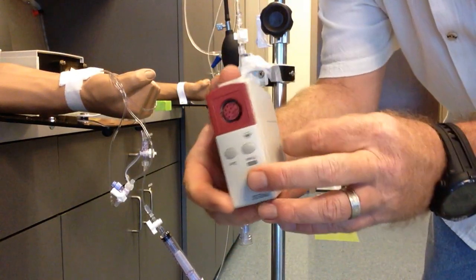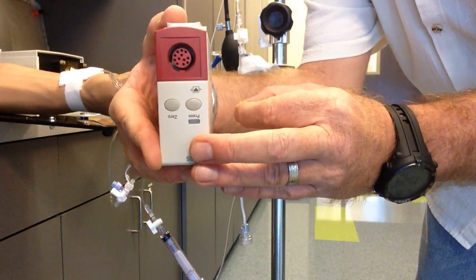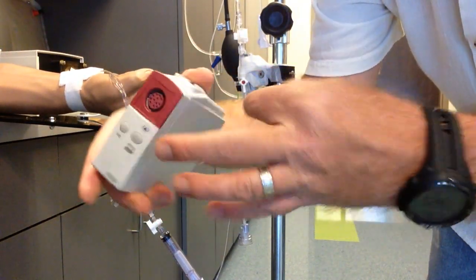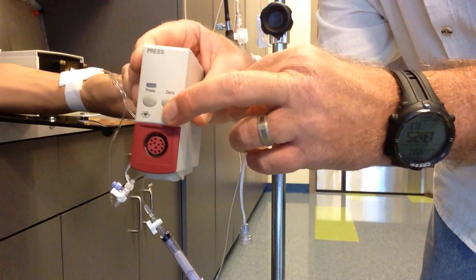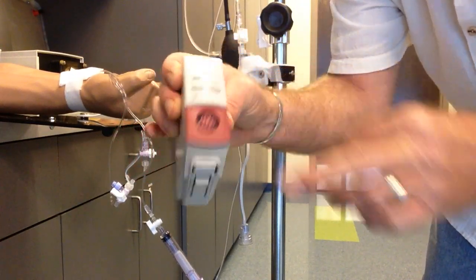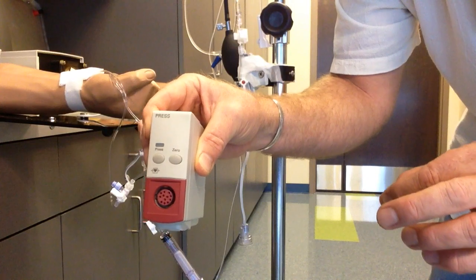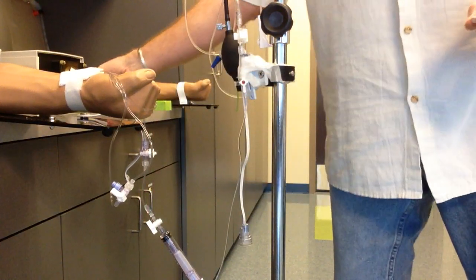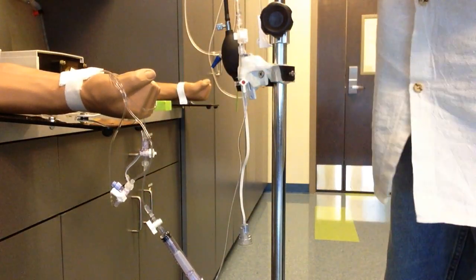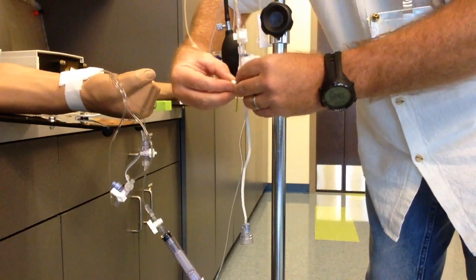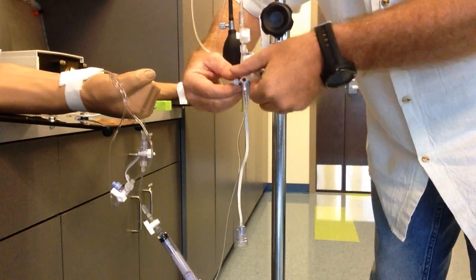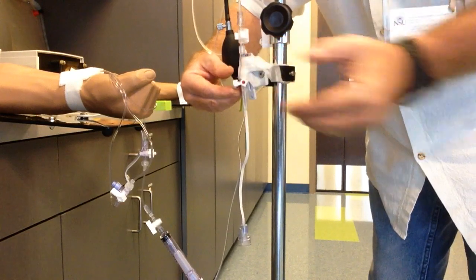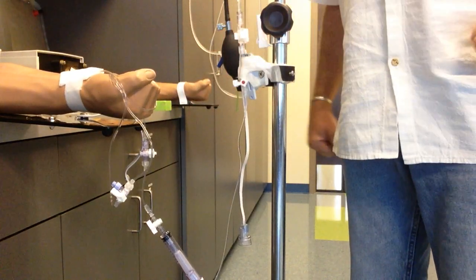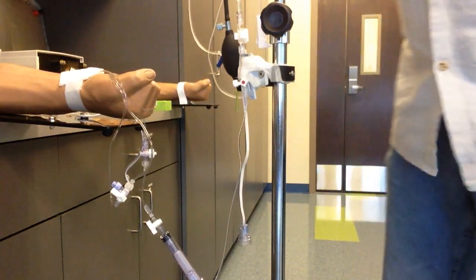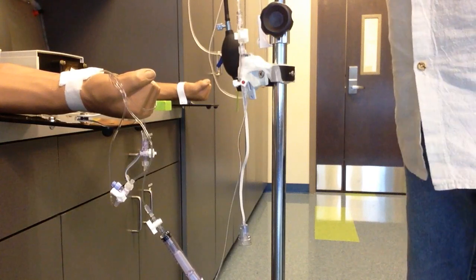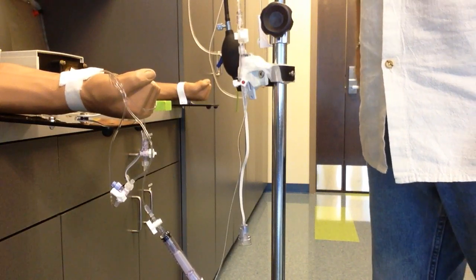And then you'll hit 0 on your monitor, which is, I have this upside down, which is right there. Boom. So I hit 0. The monitor will let you know when it's done. Replace the cap. Turn it back on. That is how you zero any type of pressure line. It is now zeroed and should be reading accurately.